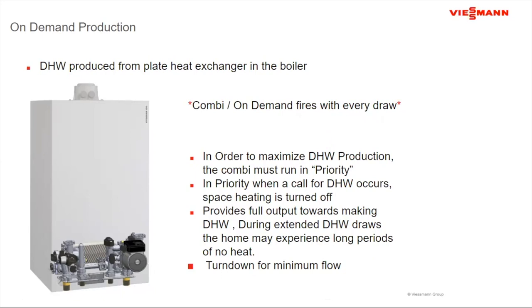If I need 0.5 gallon per minute of flow of hot water, that tells me the turndown ratio on the boiler has to get the minimum fire down around 20,000 BTUs. 20,000 BTUs will get you in the neighborhood of about 0.5 gallon per minute. So when you look at something that can go up to 200,000 BTUs, with the larger combi boilers, large turndown ratios like 10 to 1 are pretty much a must in order to get down to a reasonable low flow condition of 0.5 gallon per minute. When I start to look at sizing combi boilers, these are the kinds of things that come into play in the sizing procedure.